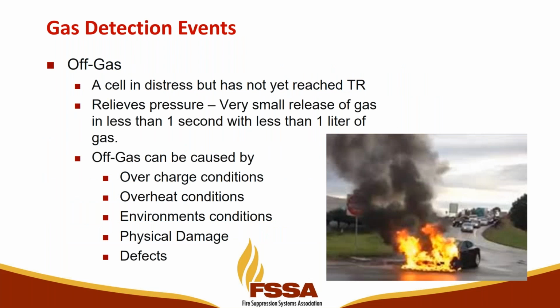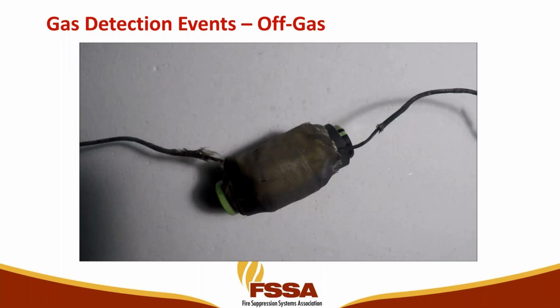So one of the things we look at is where's the initial failure mode? While the batteries take the brunt of the hit, it's actually outsourced items, overcharge, overheat, environmental conditions, physical damage that really cause the batteries to be pushed into failure mode. So before they go into thermal runaway, a distressed battery will release a very small amount of gas, less than a second, less than a liter of gas. Now pay very close attention to this video, because if you blink, you're going to miss it.